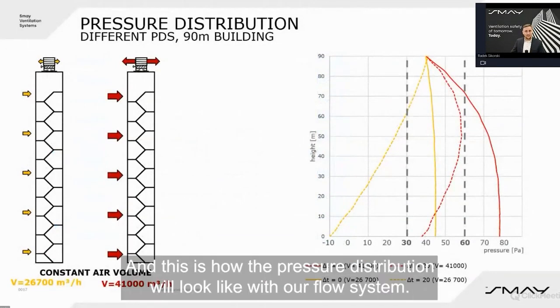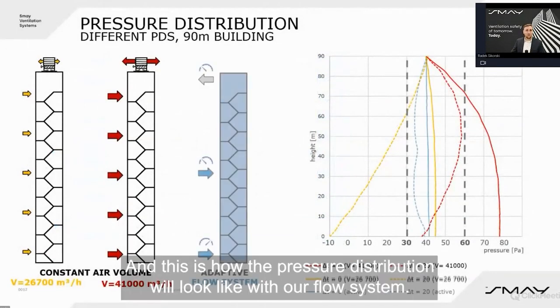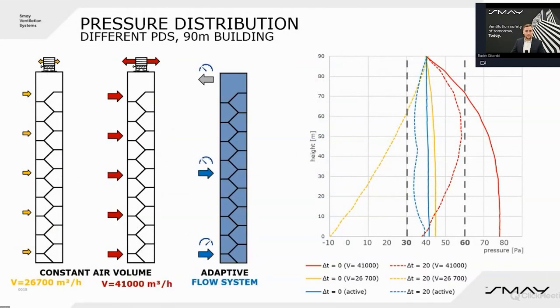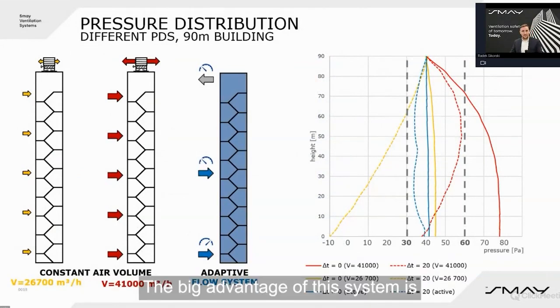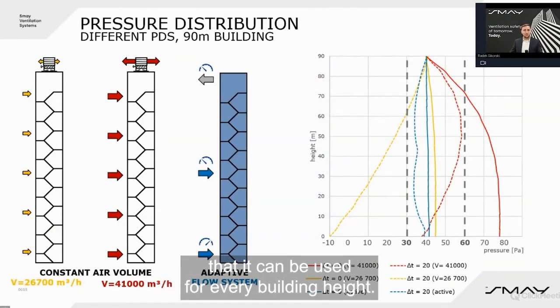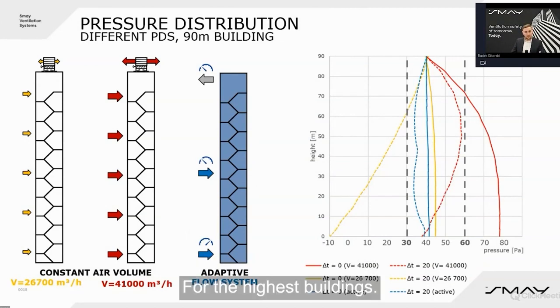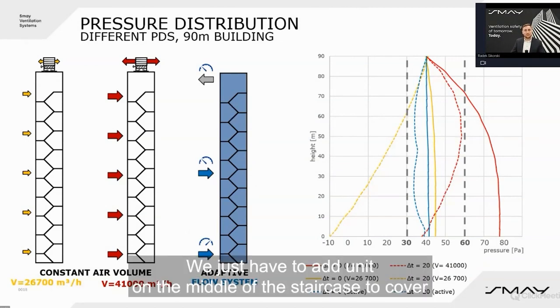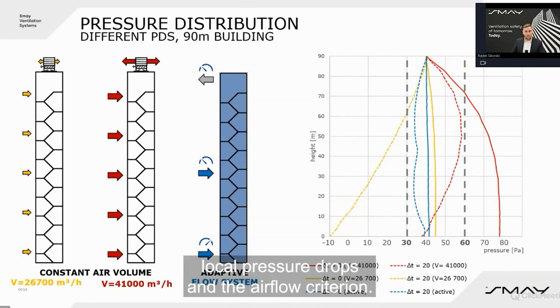This is how the pressure distribution looks with our flow system. A big advantage is that it can be used for any building height. For the tallest buildings, we simply add a unit in the middle of the staircase to cover local pressure drops and the airflow criterion.